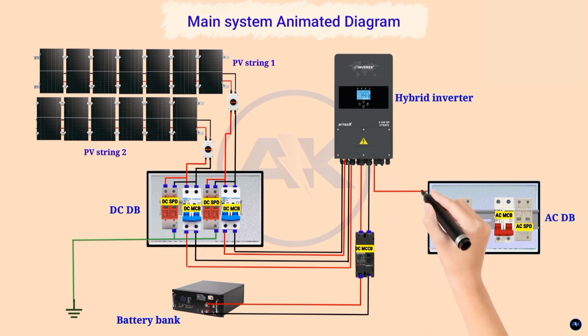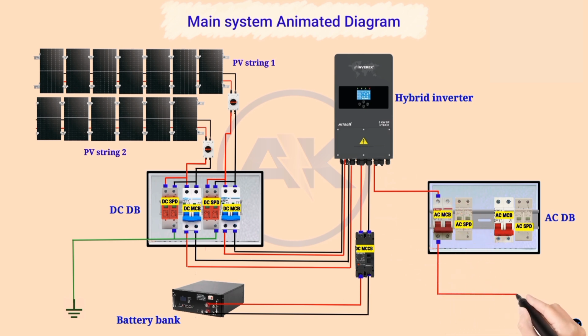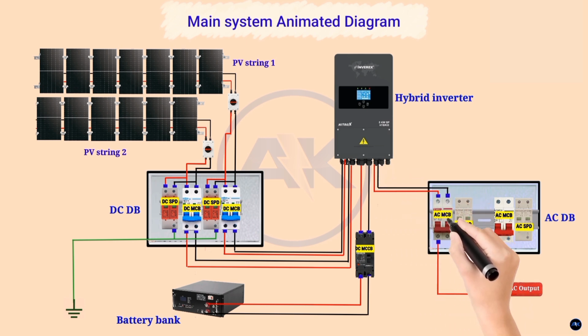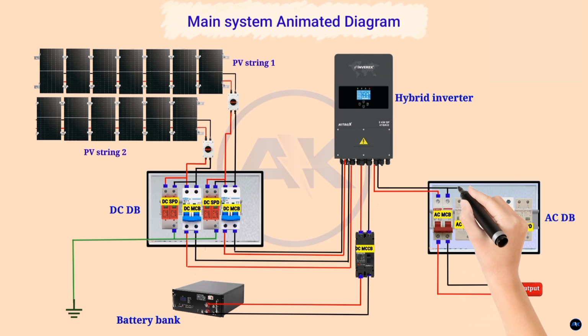Working on to the AC side, let's first connect the load on the AC output of the hybrid inverter to the AC MCB. This is where we're going to use the 8 AWG or 10 square millimeter THHN wire, or even better, silicone wire of the same gauge. And then we can wire the rest of the load or AC output of our hybrid inverter, again using the ground wires.